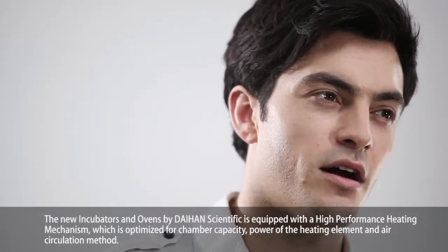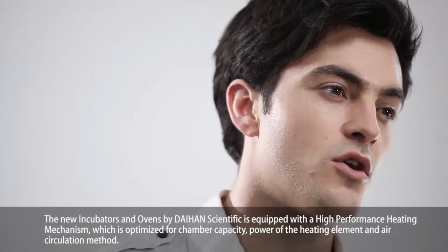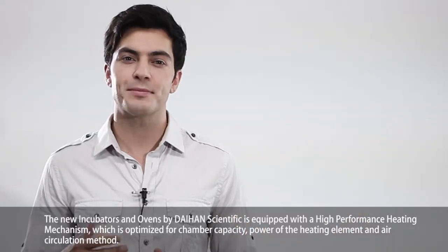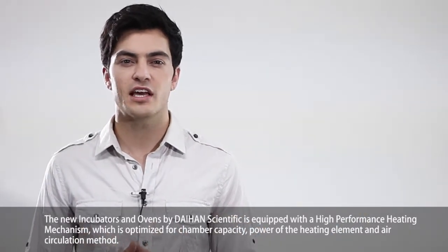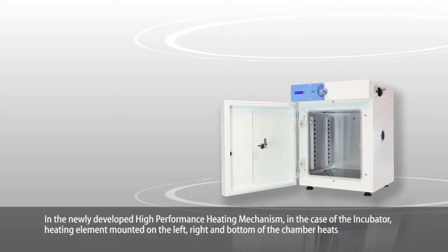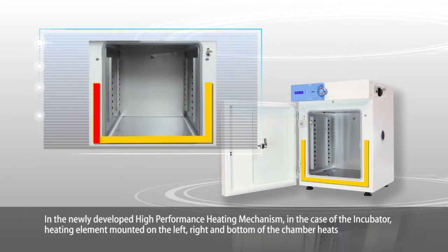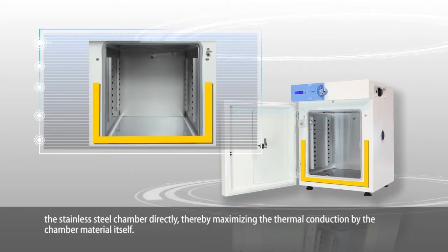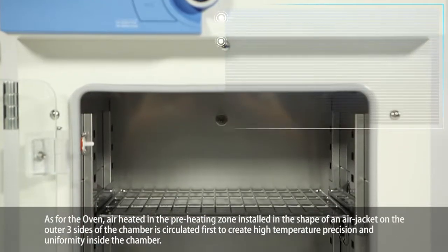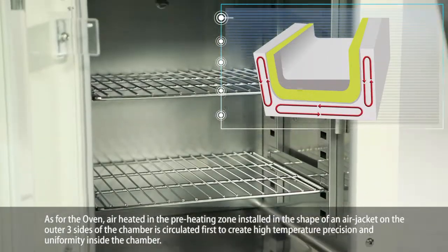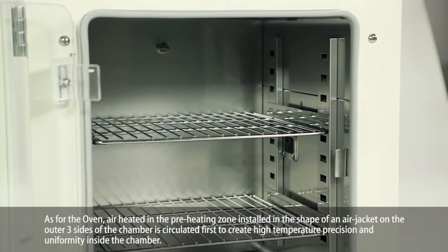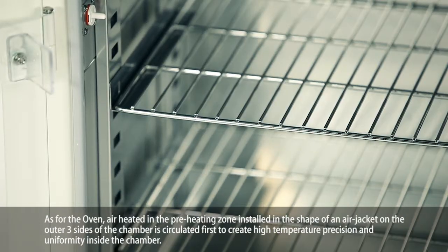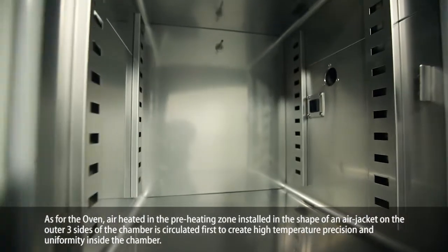The new incubators and ovens by DAIHAN Scientific are equipped with a high-performance heating mechanism, which is optimized for chamber capacity, power of the heating element, and air circulation method. In the newly developed high-performance heating mechanism, in the case of the incubator, heating elements mounted on the left, right, and bottom of the chamber heat the stainless steel chamber directly, thereby maximizing the thermal conduction by the chamber material itself. As for the oven, air heated in the preheating zone installed in the shape of an air jacket on the outer three sides of the chamber is circulated first to create high temperature precision and uniformity inside the chamber.